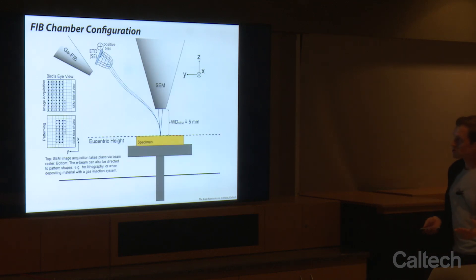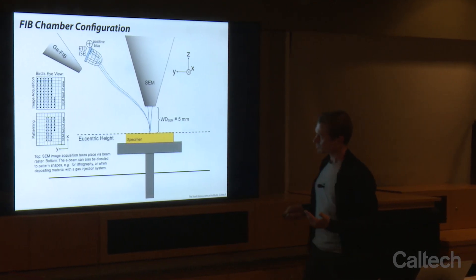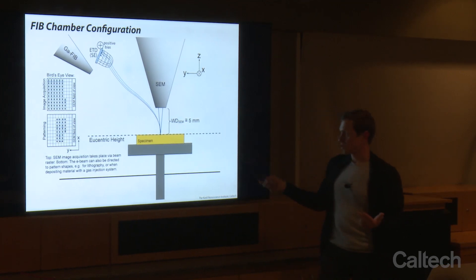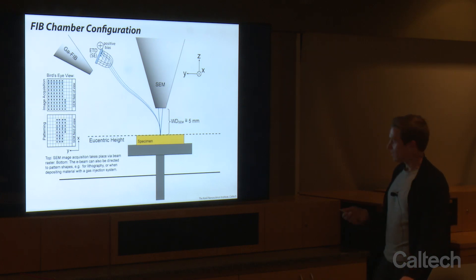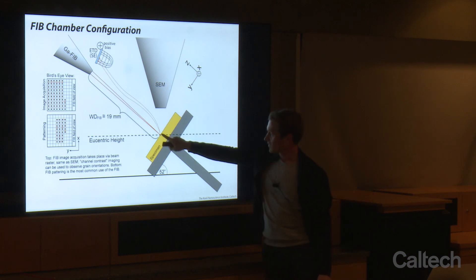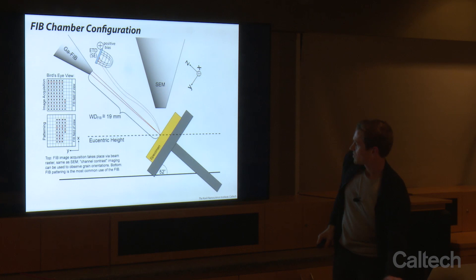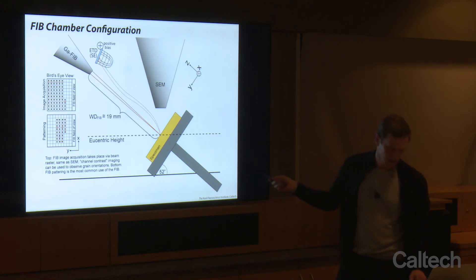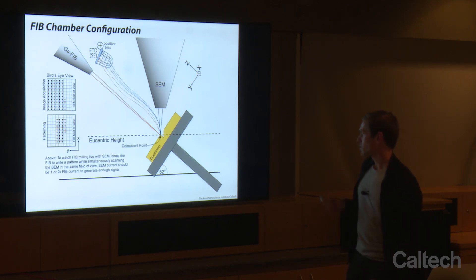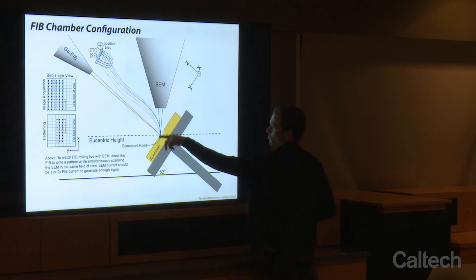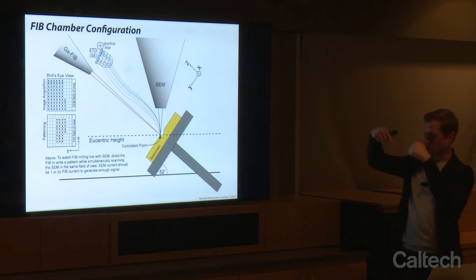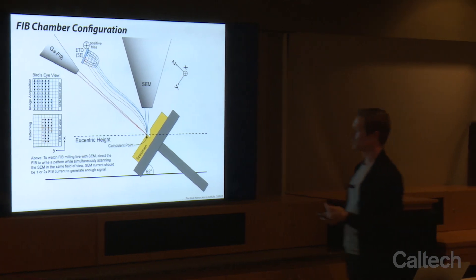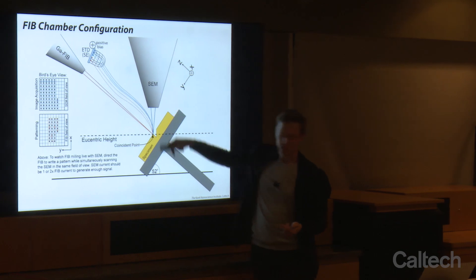We can look at the chamber configuration in cartoon form. On our systems, eucentric height is about five millimeters. The idea with eucentric height is that it's the place in the chamber where you can look at the same part of your specimen at any tilt — so if I tilt to 52 degrees, I'm hitting the same point on my specimen. It's important to be at eucentric height because ultimately we want to be able to image with the SEM what we're cutting with the gallium ion beam. We design the coincident point where the two beams cross to also be eucentric height, so we can do focused ion beam work at any tilt angle and also see it.